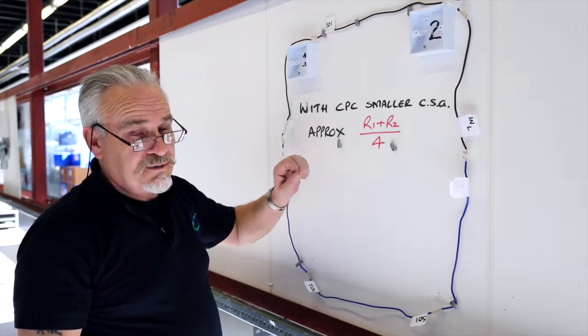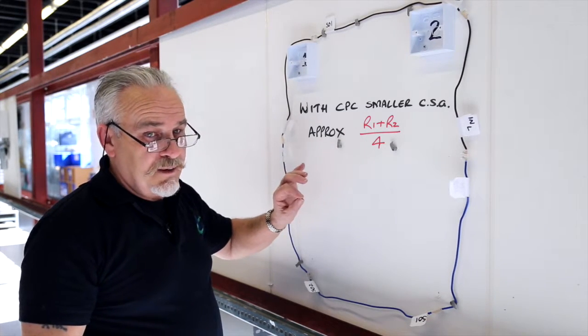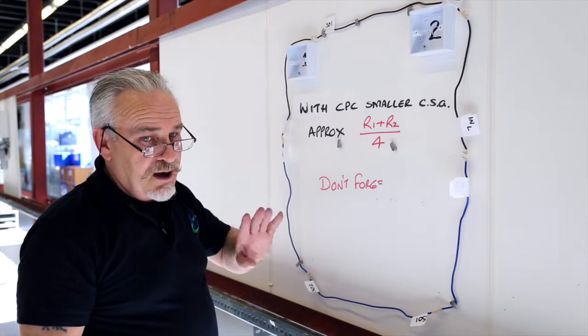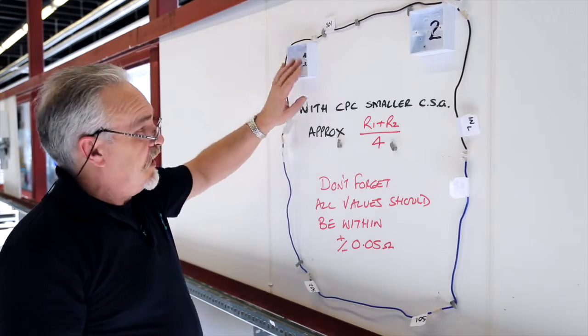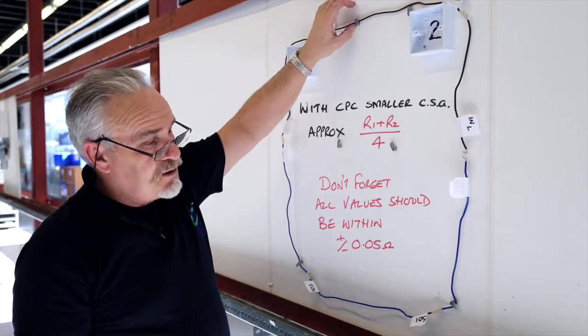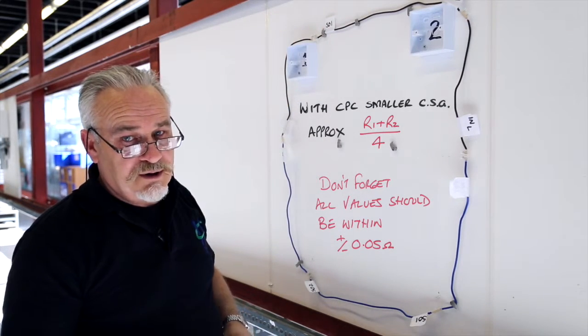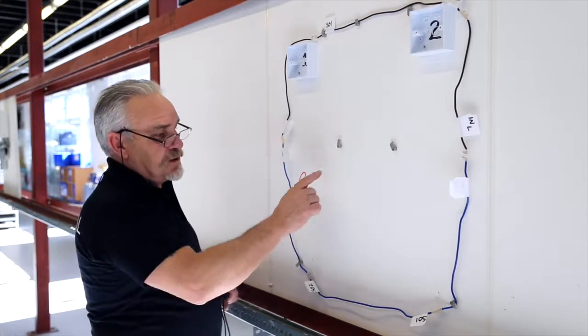Obviously when you're using twin and earth the circuit protective conductor, the CPC, is slightly smaller so you will get slightly distorted measurements. However they should all be about the same and what you'll find is that at your furthest socket you get your maximum resistance.